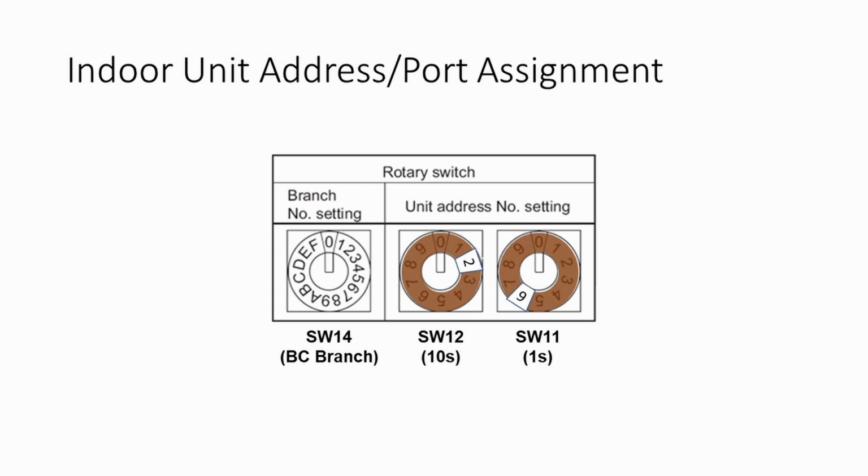You should not assume the one on the left is 10's and the one on the right is 1's. They may be mounted inversely. Make sure you look at the board to get those numbers correct. If you can't see the 1's and the 10's marking on the board, the lower number of the 2 is always the 1's and the higher number of the 2 is always the 10's.